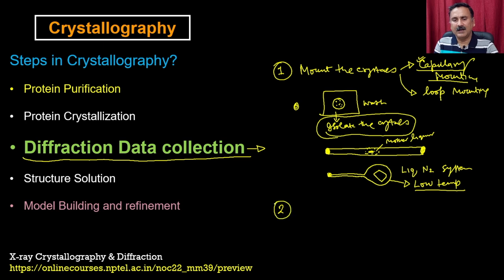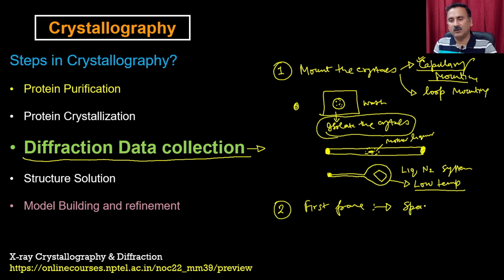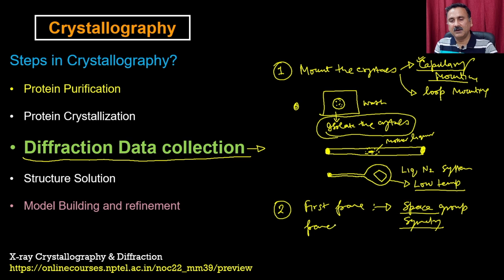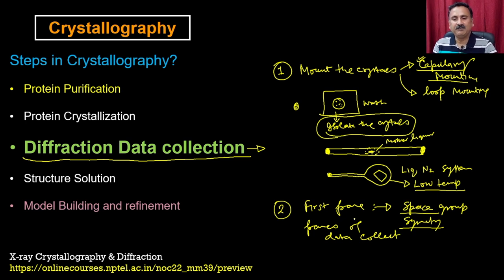In step two, you are actually going to collect the first frame. Once you collect the first frame, that will allow you to calculate the space group and it is also going to calculate the symmetry. Once you calculate the symmetry and the space group, it is actually going to tell you how many frames of data you are supposed to collect. You can imagine that if you have the crystal and if you have twofold symmetry, threefold symmetry, or fourfold symmetry, you can be able to collect the data accordingly.